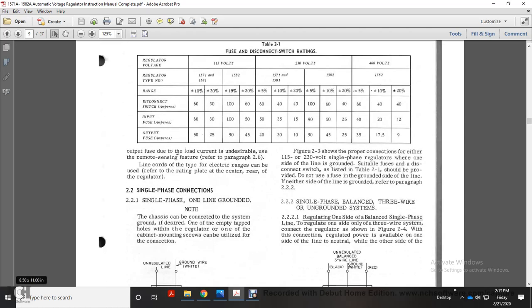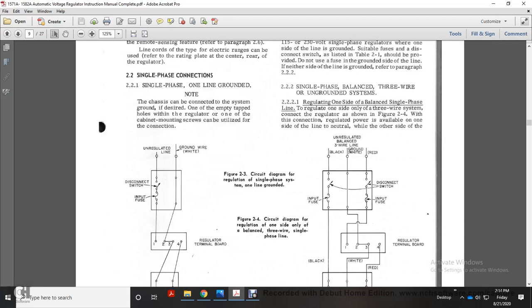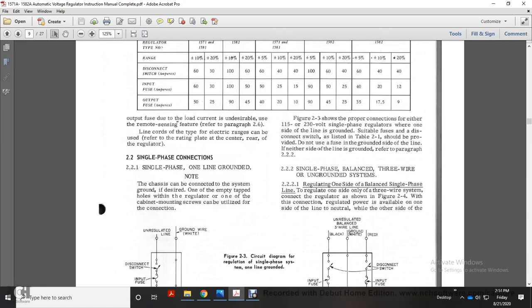Alright, 2.2, single phase connections. 2.2.1, single phase, one line ground. Note, the chassis can be connected to the system ground if desired. One of the empty tapped holes within the regulator or one of the cabinet mounting screws can be utilized for the connection. Figure 2.3 shows the proper connections with either a 115 or 230 volt single phase regulator with one side of the line is grounded.